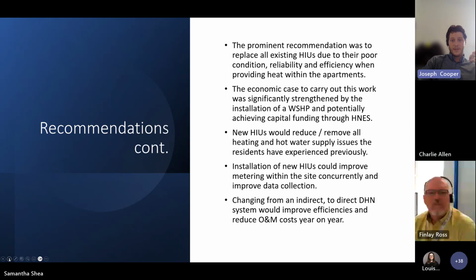New HIUs would reduce/remove all heating and hot water supply issues the residents have experienced previously. An installation of new HIUs could improve metering within the site concurrently and improve data collection. A lot of the work around that would be to relocate meters outside of the units, and that would help us identify which are basically defunct, where we've got gaps in data and where we need to replace meters in the future, and give us more visibility on the metering side of things. And changing from an indirect to a direct district heat network system was a recommendation as well, which would improve efficiency and reduce operating and mechanical costs year on year.